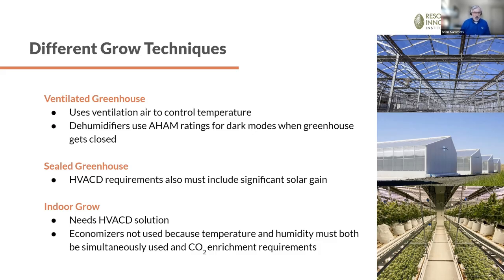Economizers are typically not used like they might be in comfort cooling, because it's rare that outdoor air is at the right temperature and humidity. In a lot of cases, particularly cannabis, you're pumping CO2 into the room to help the plant grow, and if you bring in outdoor air, you're just diluting the money you spent on CO2. There are also issues about introducing pests from outside, wild hemp spores, and things of that nature.